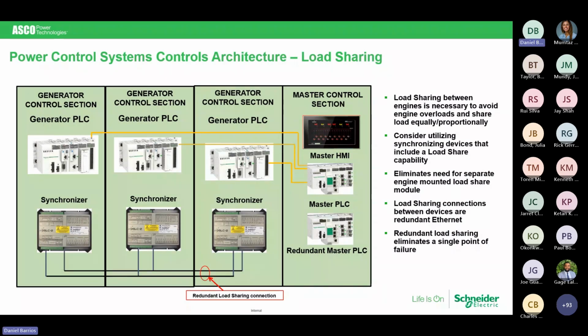When you look at the topography of what we're dealing with here, you can see that we have redundant load sharing controls and redundant communication controls and such. When you go to our factory to do a factory witness test, which I highly recommend if you have the opportunity to do so, they're not only going to operate the gear for you, but in each of our sequence of operation, there are criteria of failure.